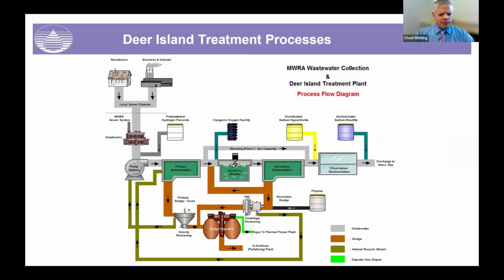This is a process schematic of the Deer Island treatment system. So we get our flow from 270 miles of collection interceptors from the 43 communities. We have 4 off-island headworks and 1 on-island headworks facility, ranging in size from 125 million gallons per day to 400 million gallons per day. The untreated wastewater is then transported under Boston Harbor through deep rock tunnels. Deer Island draws the wastewater through the tunnels with large pumps on Deer Island, ranging from 600 horsepower to 3,500 horsepower. Deer Island is an activated sludge pure oxygen secondary treatment plant, utilizing sodium hypochlorite for disinfection.